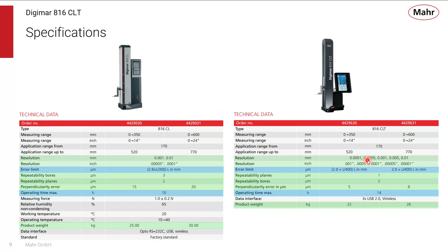In terms of hardware changes, this height gauge, the 816 CLT, has a completely new design. As you can see on the left side, the weight reduction is achieved by using a stable aluminum column instead of steel, giving that 6 to 8 pounds weight reduction.